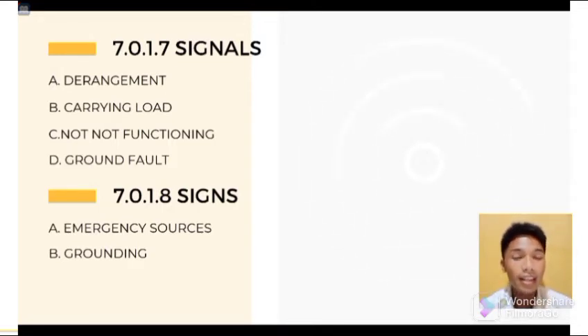To indicate derangement of the emergency, this is the derangement. Letter B, carrying load, to indicate that the battery is carrying load. C, not functioning, to indicate that the battery charger is not functioning.